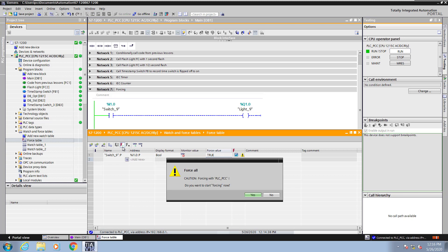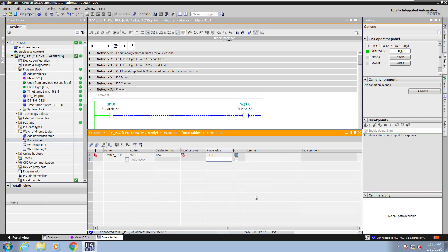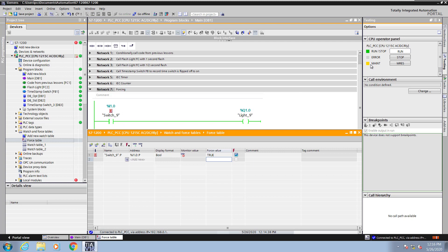In this case, the value is being written to the card and then that's being copied into the process input image area. So now you will see the logic being updated, but there is also an F above the switch nine that indicates the value is being forced and the yellow maintenance light is on indicating the value is being forced as well.